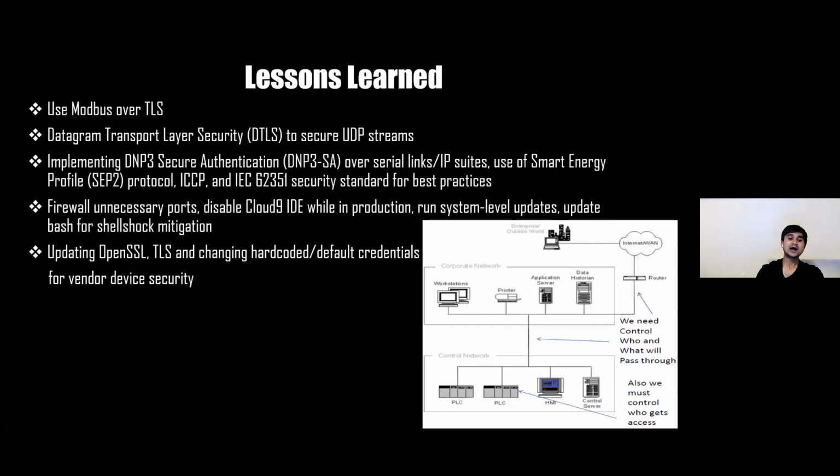There is no harm in implementing Modbus if it is done correctly, but no plain text. Regardless of serial Modbus RTU or Modbus over TCP/IP, I suggest adding an extra layer of transport layer security, TLS, for encryption. UDP itself is unreliable, but even if you're moving forward with UDP and have sensitive information, you can use secure protocols like DTLS, Datagram Transport Layer Security, for maintaining privacy.